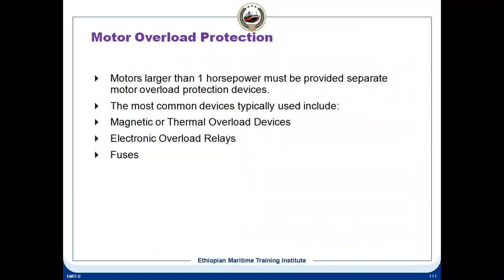Okay, the next topic is overload protection. We know a motor has overload protection. The overload protection relay is always connected in series with the control supply of the magnetic contactor. Whenever an overload takes place, it cuts off the power for the magnetic contactor, the starter trips, and the motor will stop. Basically there are 3 types of overload relays. Most commonly used are magnetic type, thermal overload type, electronic type, and fuses.